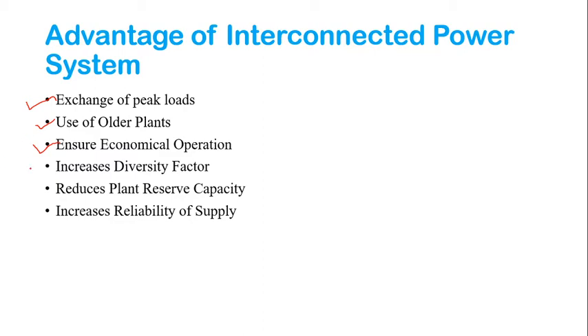Next is increased diversity factor. The load curves of different interconnected stations are generally different, so the maximum demand on the system is much reduced compared to the sum of individual maximum demands on the different stations. In other words, the diversity factor of the system improves, thereby increasing the effective capacity of the system.